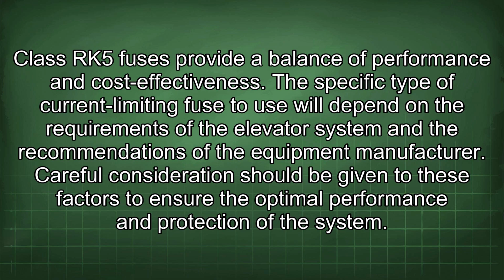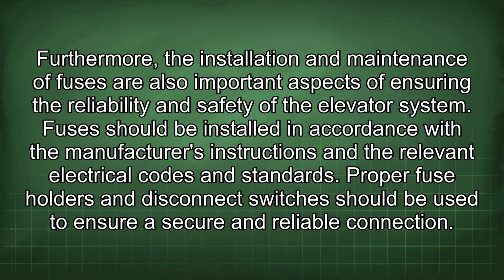The specific type of current-limiting fuse to use will depend on the requirements of the elevator system and the recommendations of the equipment manufacturer. Careful consideration should be given to these factors to ensure the optimal performance and protection of the system. Furthermore, the installation and maintenance of fuses are also important aspects of ensuring the reliability and safety of the elevator system. Fuses should be installed in accordance with the manufacturer's instructions and the relevant electrical codes and standards.